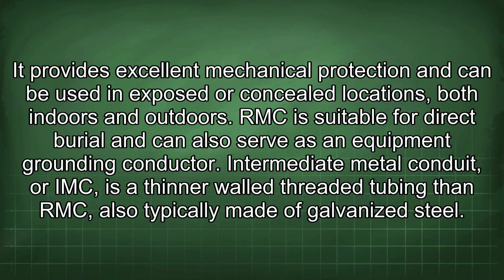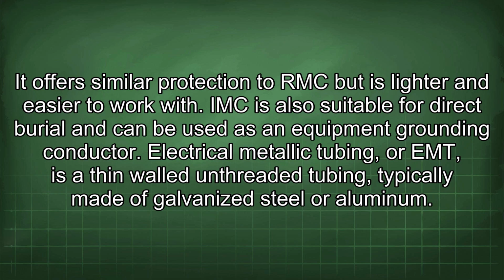Intermediate metal conduit, or IMC, is a thinner-walled threaded tubing than RMC, also typically made of galvanized steel. It offers similar protection to RMC but is lighter and easier to work with. IMC is also suitable for direct burial and can be used as an equipment grounding conductor.